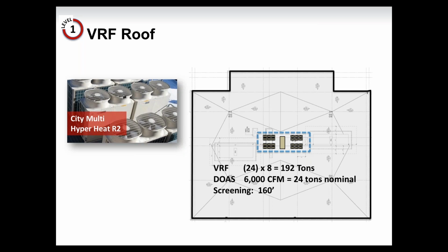24 8-ton hyperheat units equal 192 tons of cooling. You'll need a DOAS unit. 6,000 CFM is the nominal 24 tons of cooling. That is 216 tons. We tried to equate to the rooftop portion of the bid, which was 210. Because of the module sizing of the VRF, we're slightly over. I wanted to be conservative on the VRF portion of the pricing, so we have a few extra tons of cooling in the VRF solution, just based on module size.